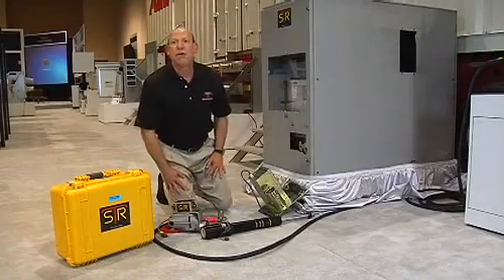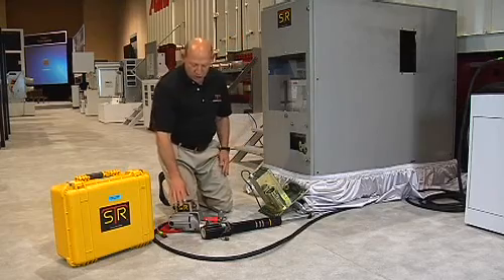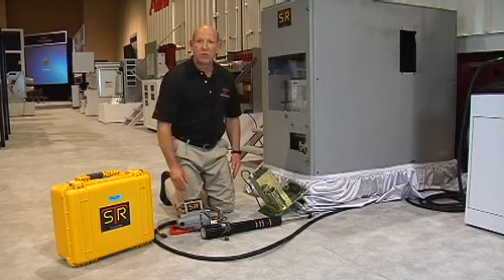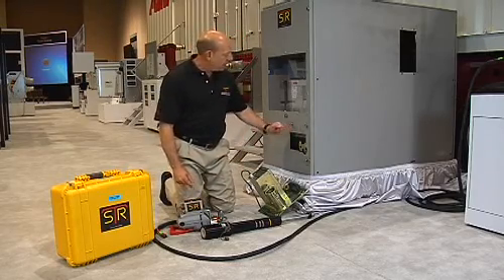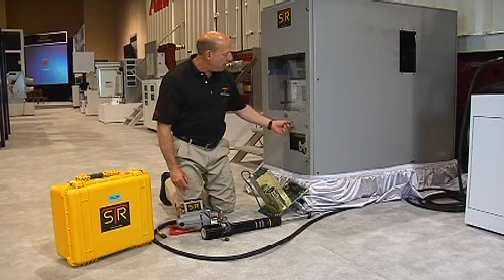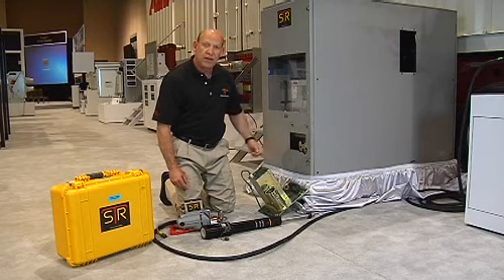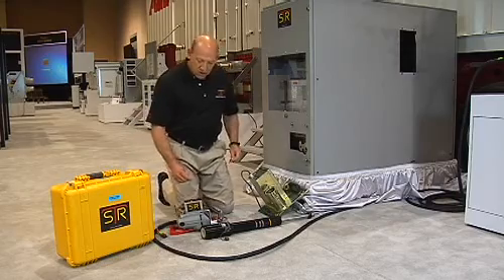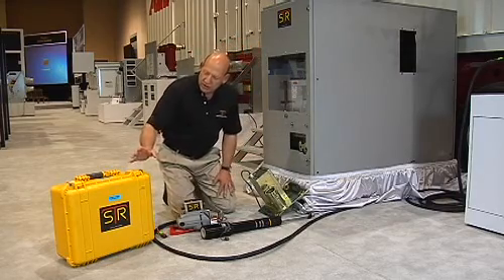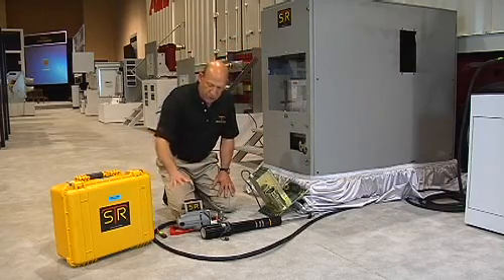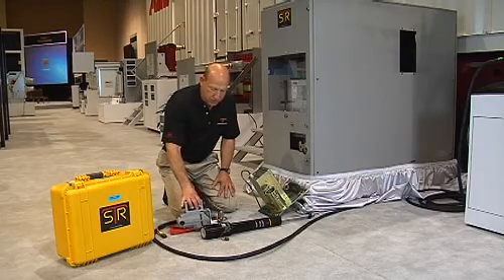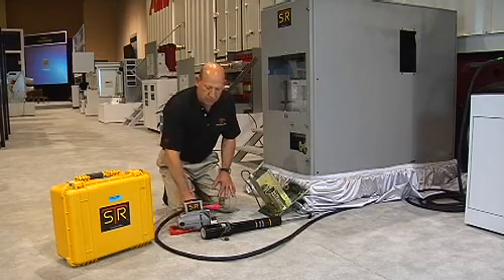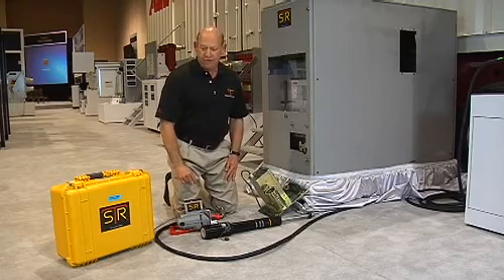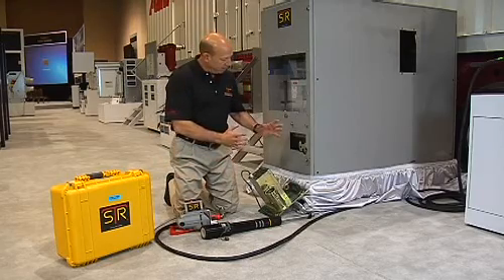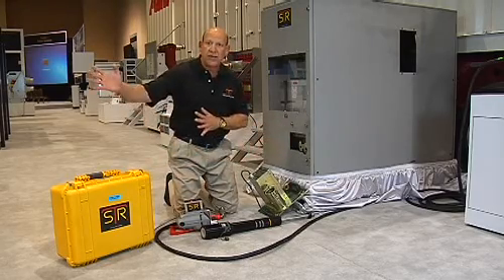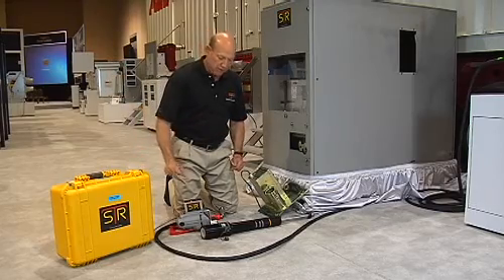This is the Safety Rack model SRH Universal Circuit Breaker Racking Tool. The application today is the ABB ITE 5HK250 circuit breaker. The Safety Rack product consists of a system controller, a power drive motor, and a power comm cable. The power comm cable is 35 feet, and that allows you to connect from your working point out to a safe distance to connect to the system controller.